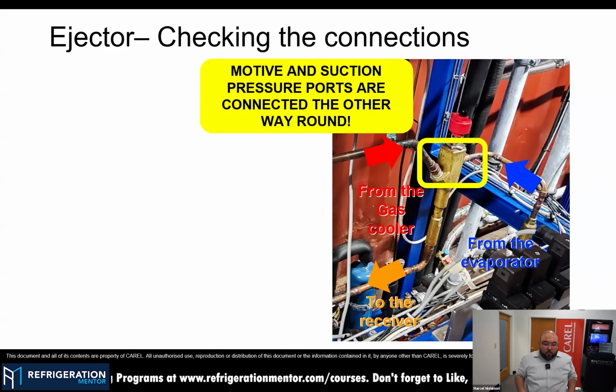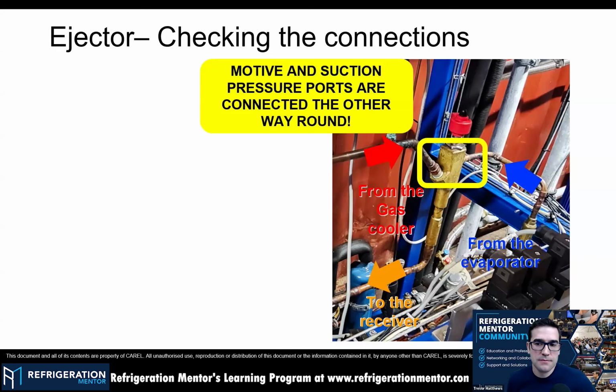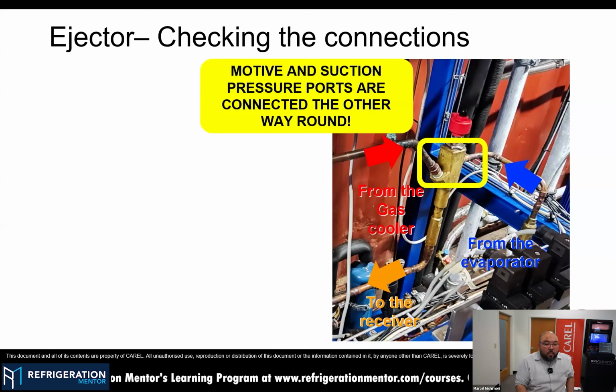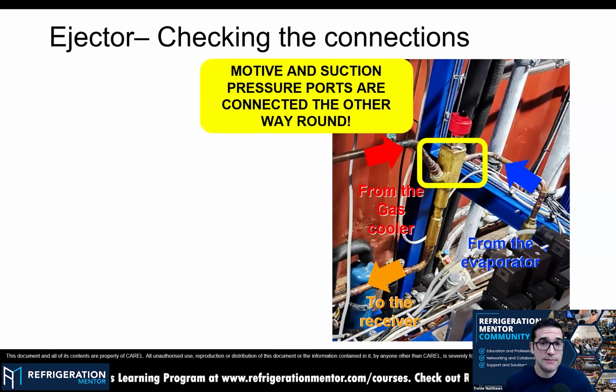I mean, internally in the ejector, you will see that the piece is not so small, because we have internal piping to make sure that we have the proper fluid dynamics inside it. So when the refrigerant goes out of the ejector from the outlet, it is already mixed and at the right pressure and fluid dynamics. From that point and beyond, you can make the curves you need. No problem. Perfect. For sure, the more curves you add, the more pressure drop you have, so this is more on the design side to avoid pressure drops. Yeah, we don't like pressure drops in any system.